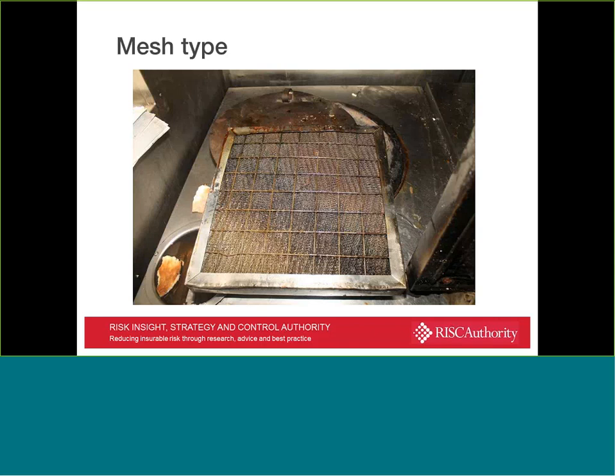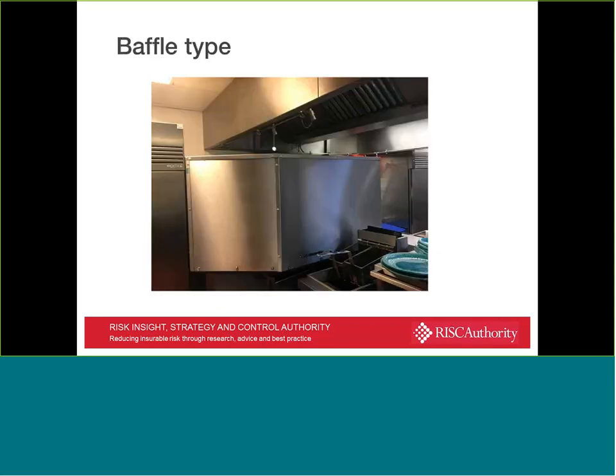And they're simply there to collect the majority of oil and grease as it passes from the cooking surface through, and always drawn through into the extract ductwork. The issues associated with that are that they do collect a huge amount of oil and grease, and they do need very, very regular cleaning as a result of it. And the fact that they collect so much grease in the way that they do does mean that the likelihood of ignition and a serious blaze is quite high with these types of filters.